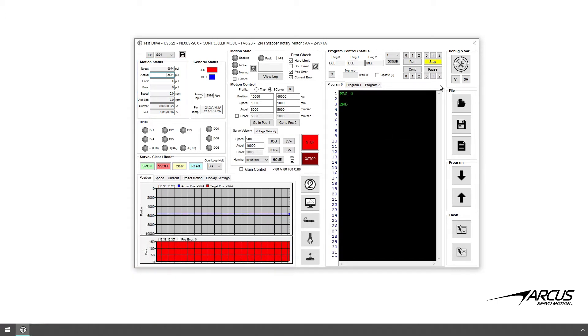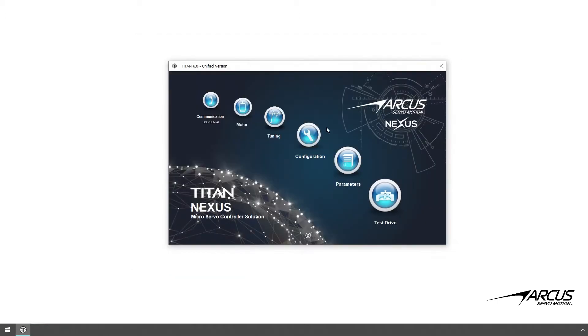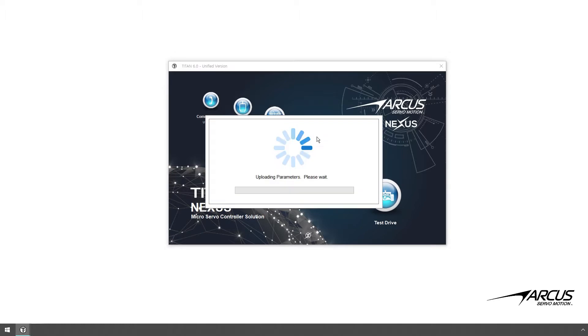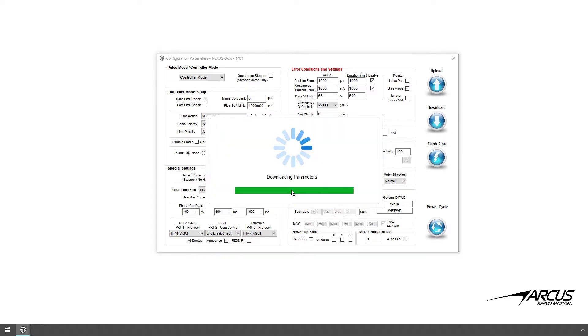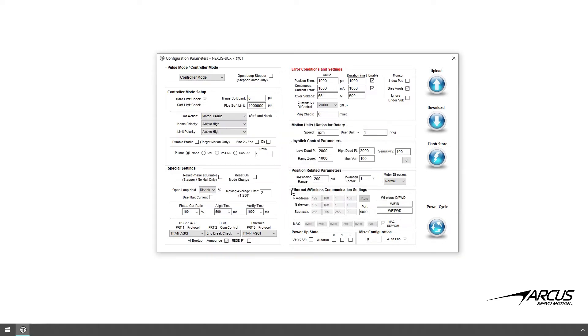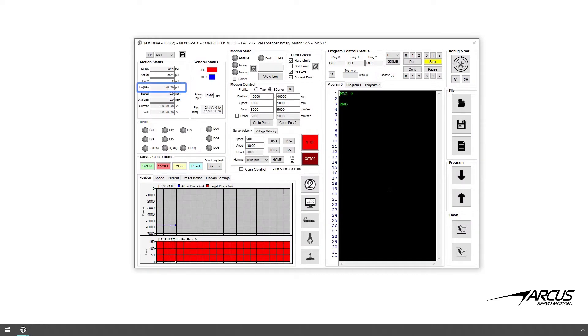For stepper motors, if bias angle compensation is enabled, the bias angle value will show next to the position error in parentheses. With bias angle compensation and monitoring enabled, the motor will be able to move at optimal torque performance especially in high speed. Bias angle monitoring is also used to detect any encoder drifts that may occur when you have noise on the encoder lines. Note that if the bias angle goes above 60 degrees the motor will go into a fault.